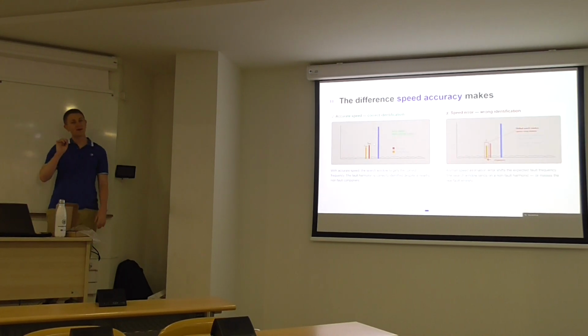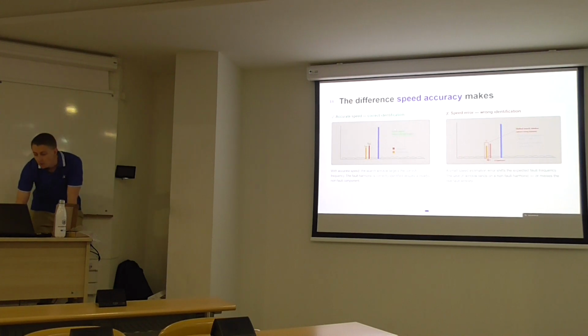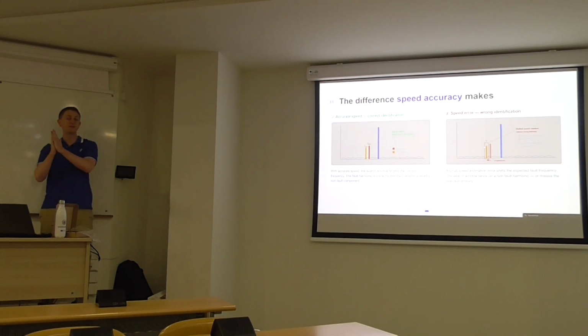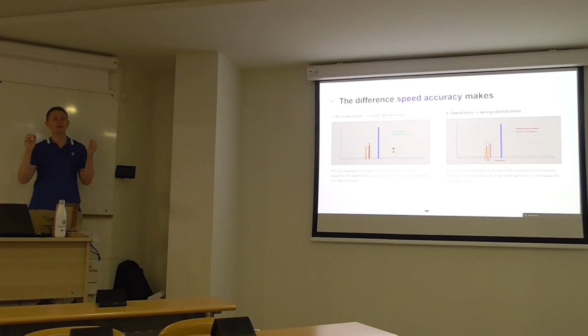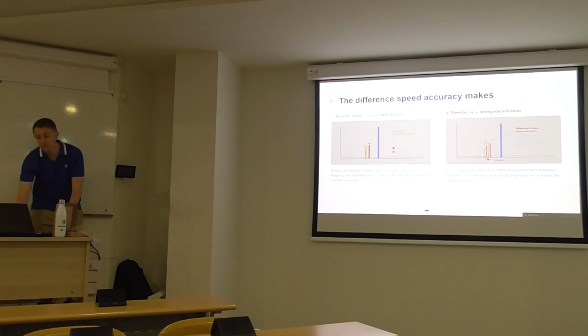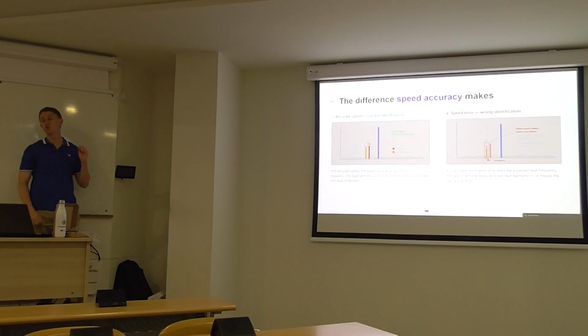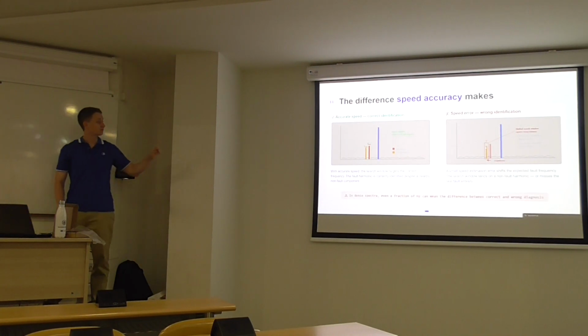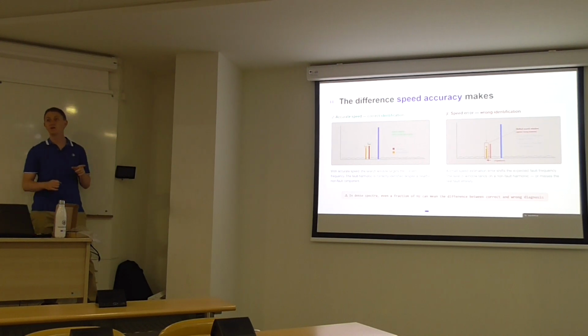However, if we don't have a precise estimation of the speed, we can think that the fault harmonic is that one here. Because the expected frequency has moved, we consider that that is where the broken bar harmonic should be, but in fact what we have here is just a non-fault related harmonic. So we can provide a wrong diagnosis based on that information. So accurate speed estimation is super important. Just a reminder, in intense spectra, like the ones you will have in real industrial conditions, or when the motor is fed with a variable frequency drive, even a fraction of a hertz can make the difference between a good or wrong diagnosis. And I will show you a real example of that.